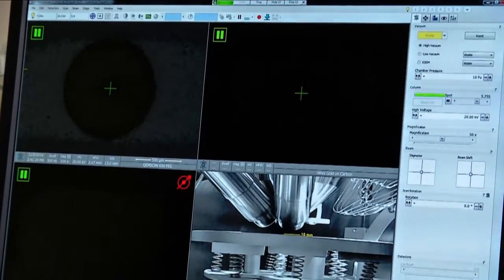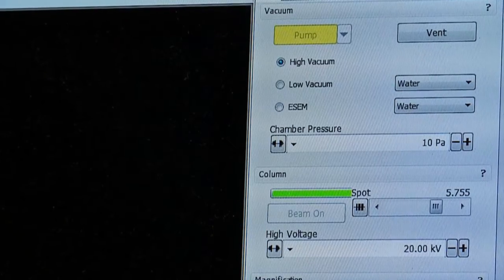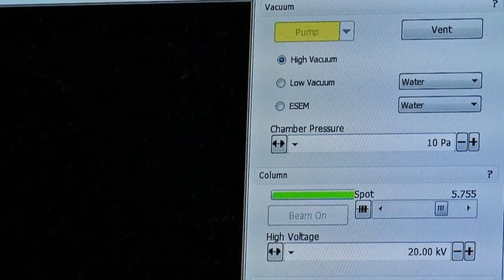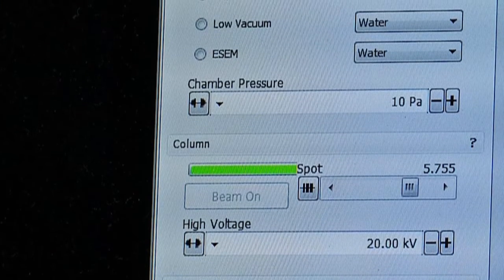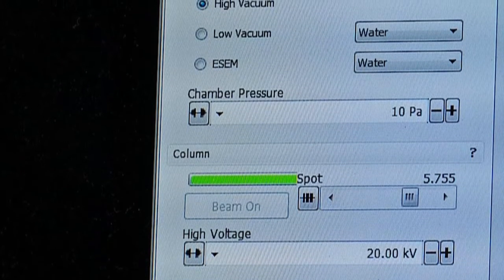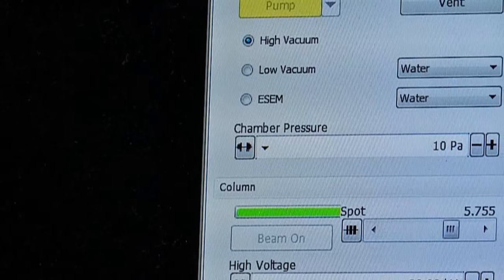The yellow and green colors. The green shows that the top of the column is kept at a vacuum, whereas the bottom chamber is orange because there's no vacuum in it. So once this turns green, we'll be safe to switch on the electron gun.